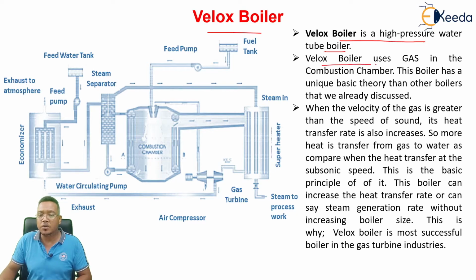The Velox boiler uses gas in the combustion chamber as a fuel. The boiler has a unique basic theory compared to the other boilers that we have already discussed. In the Velox boiler, we will use the gas at a very high velocity. The velocity of the gas will be more than the velocity of sound. Why are we using the gas at a very high velocity?